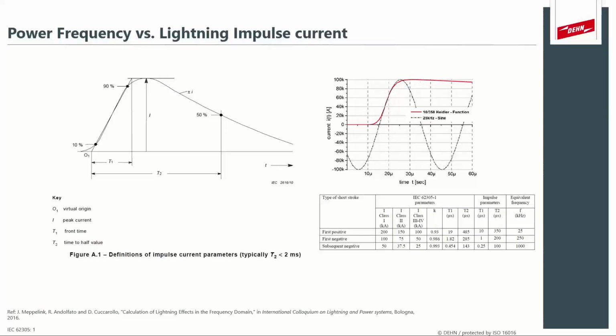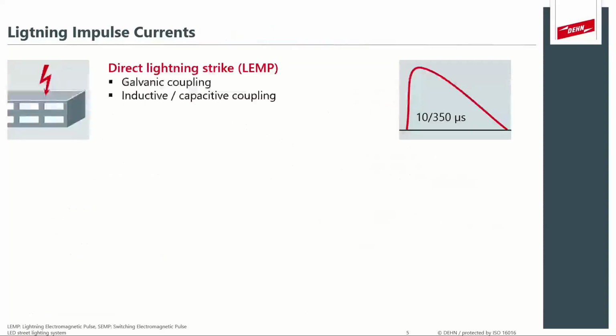Now, if we dig a little bit deeper into the wave shapes and how we characterize it, I described that for the first positive stroke, which carries the most damage or the most energy, we talk about a 10 by 350 wave shape. And that is known as a direct lightning strike. So that's something that terminates directly onto your building or your installation, and so on. Now, this is not something that happens frequently. This is something that can happen once every 5 years or 10 years, depending on the calculation or the risk analysis conducted for that structure, but it's not something that happens commonly or frequently every year.